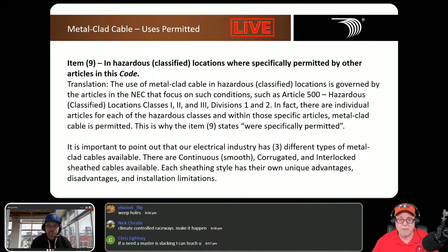Item number 10, in dry locations and embedded in plaster finish on brick or other masonry, except in damp or wet locations. So, Jay, this is saying, look, MC is a dry rated product. You can use it anywhere that it's a dry location, in the walls or a dry location. Okay? Exterior walls, in the walls is a dry location. Interior walls, dry location. Perfectly fine. It also says, and I'll also let you do this, Jay. I will let you take that MC and I will let you embed that in plaster finish, whether it's on brick or other masonry, unless it's a damp or wet location, because that material, plaster and things like that, tend to absorb moisture. And we don't want this armor and all this sitting around in contact with constant moisture.